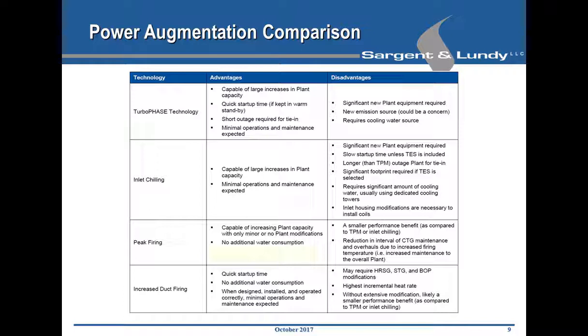And our assessment there is that all those technologies have advantages and disadvantages, but if you look at some of those items that we list on that page, you can see that Turbophase compares quite well because it's a significant increase in plant capacity. It's a quick startup time and a very short outage. If you take, for example, inlet chilling, especially if you have thermal energy storage associated with inlet chilling, some tank that might take up to 6 to 12 months to install, whereas Turbophase obviously can be installed in a much shorter time period. Also, capital cost is quite competitive in comparison to inlet chilling.